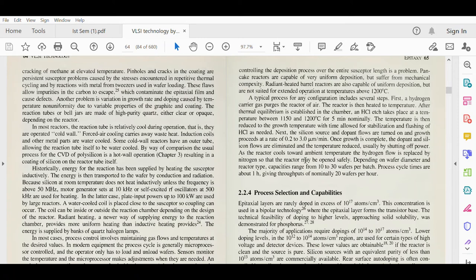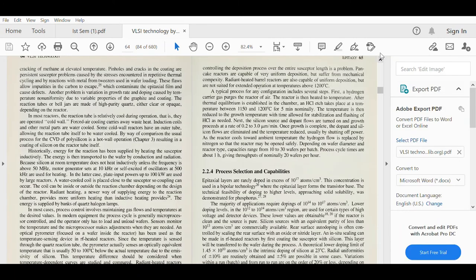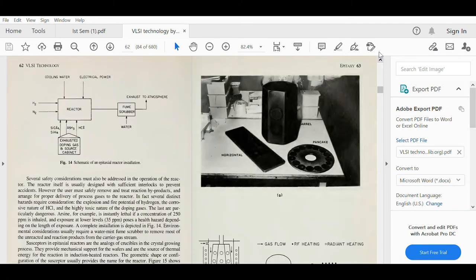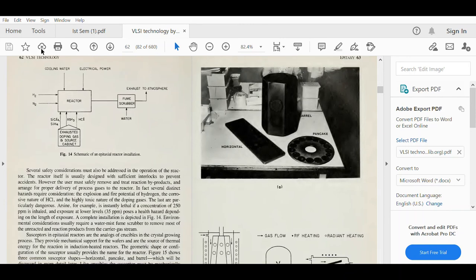As the reactor cools toward ambient temperature, hydrogen flow is replaced by nitrogen so that the reactor may be opened safely. Let me show you that picture again so we can relate it more easily to what this paragraph is discussing. This is the reactor. We are talking about this hydrogen gas, so initially hydrogen gas is provided at a higher temperature. Cooling water is provided, electrical power is there. Then when the process goes further, the temperature is reduced.